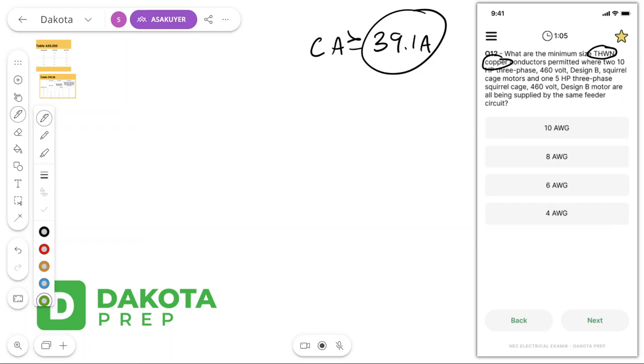All right. Now that's a little confusing sometimes, because likely what's going to happen is that breaker that's out in front, that's protecting these conductors, it's not actually protecting them. It just seems like it is. It's just for short circuit current. We talked about that before. These conductors are likely to have an ampacity smaller than the breaker or fuse that's out in front, completely legal, completely fine. Remember, that breaker or fuse is only there for short circuit protection. Number 8. That's our correct answer.